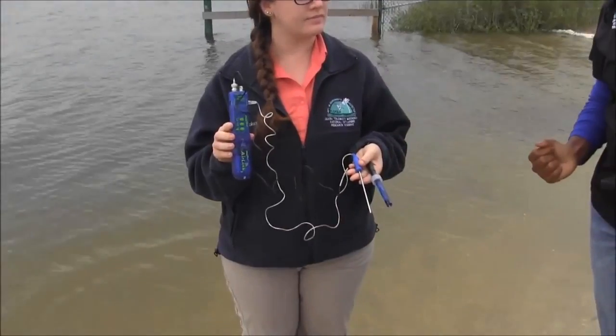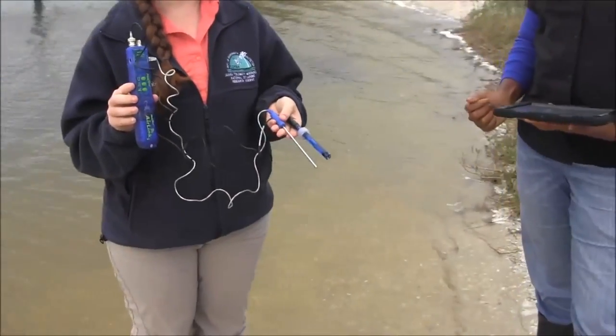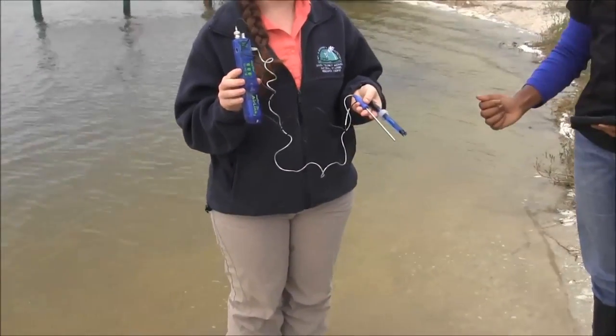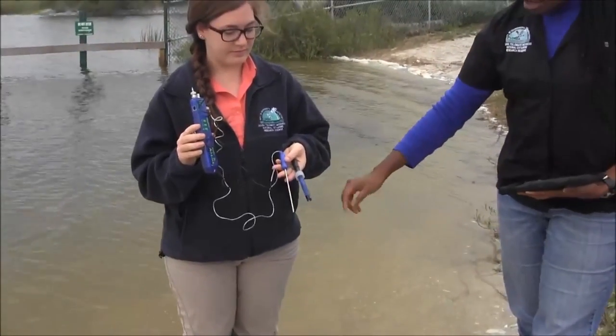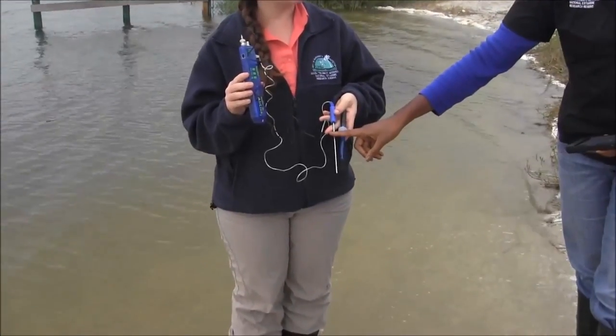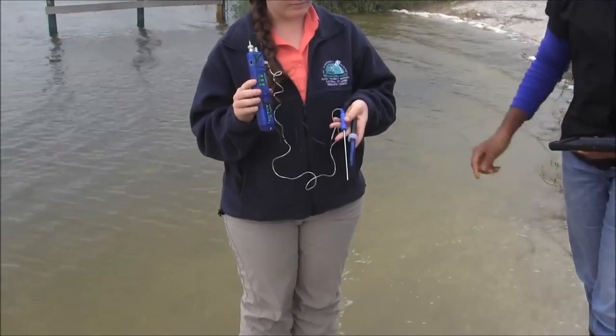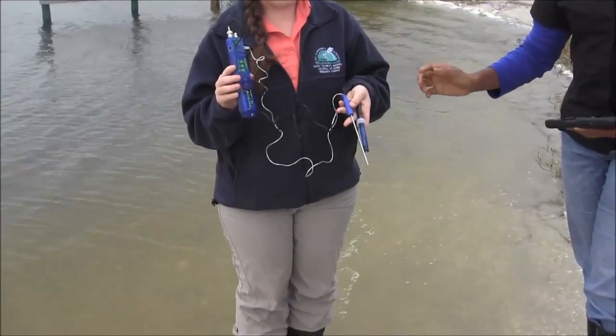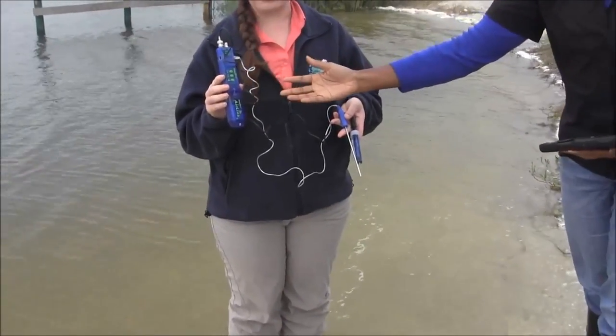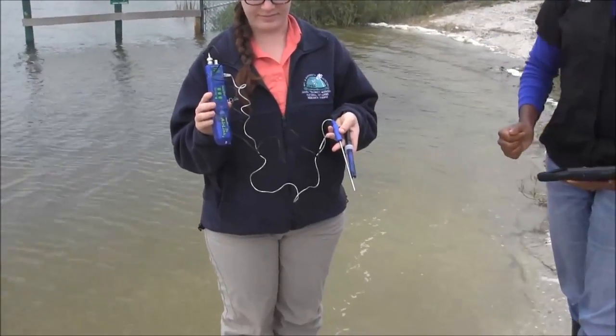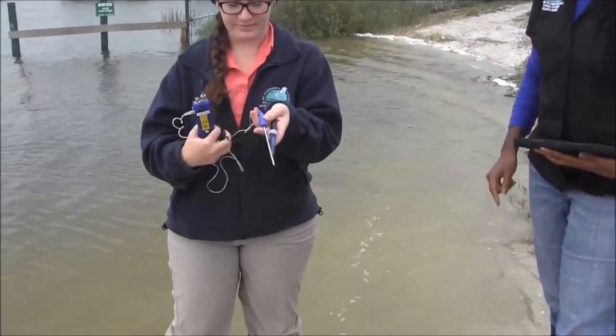All right, so Caitlin's ready to go ahead and take our water sample. When you're taking your sample, make sure that you dip your probes at least 3/4 the way past in the water, but don't get your wires wet, and make sure that you don't ever get the actual Bluetooth device wet. That should not ever go in the water. All right, go ahead and dip your probes.